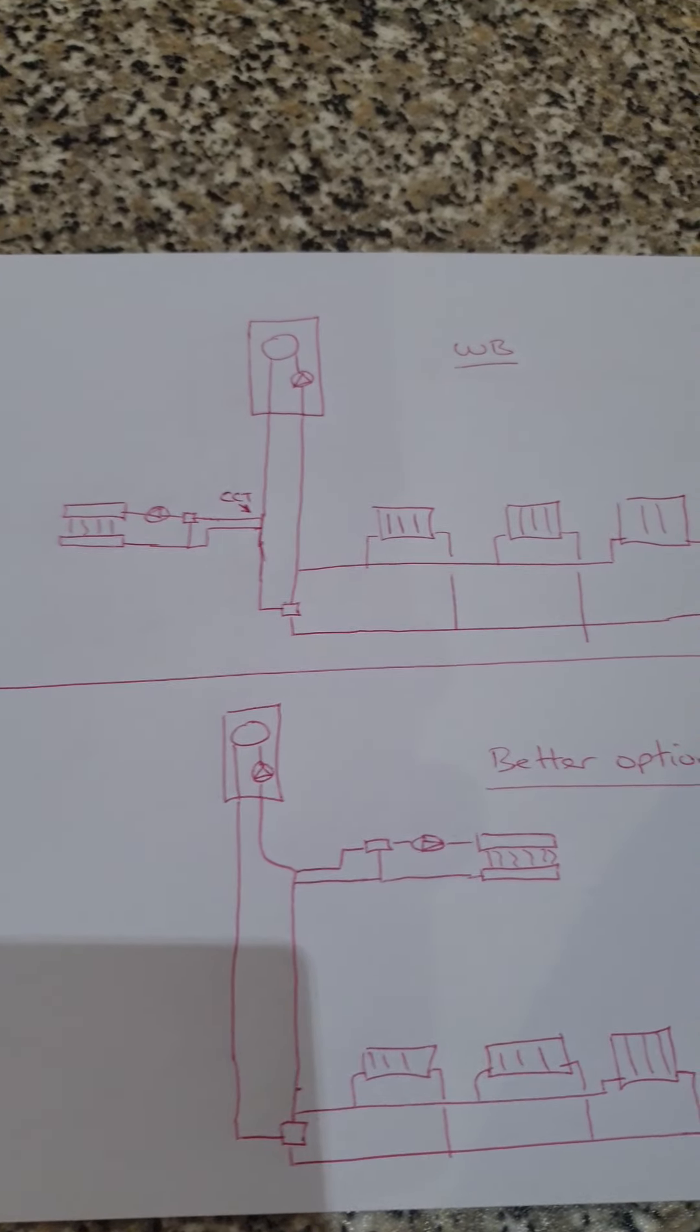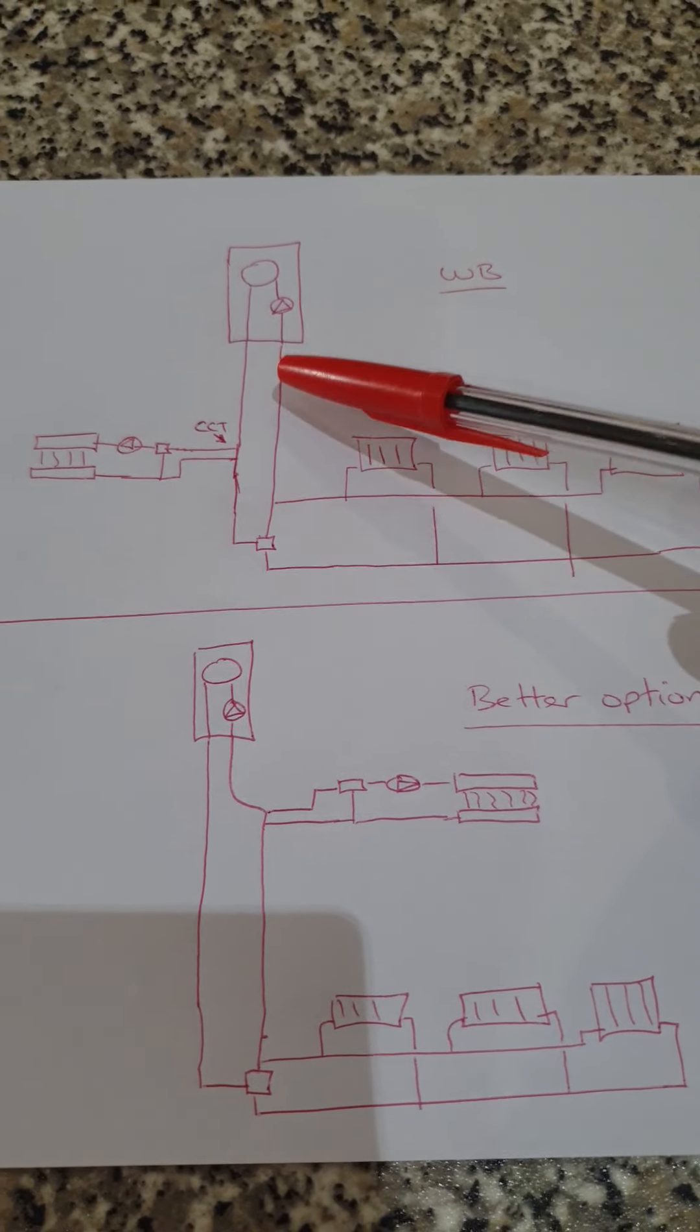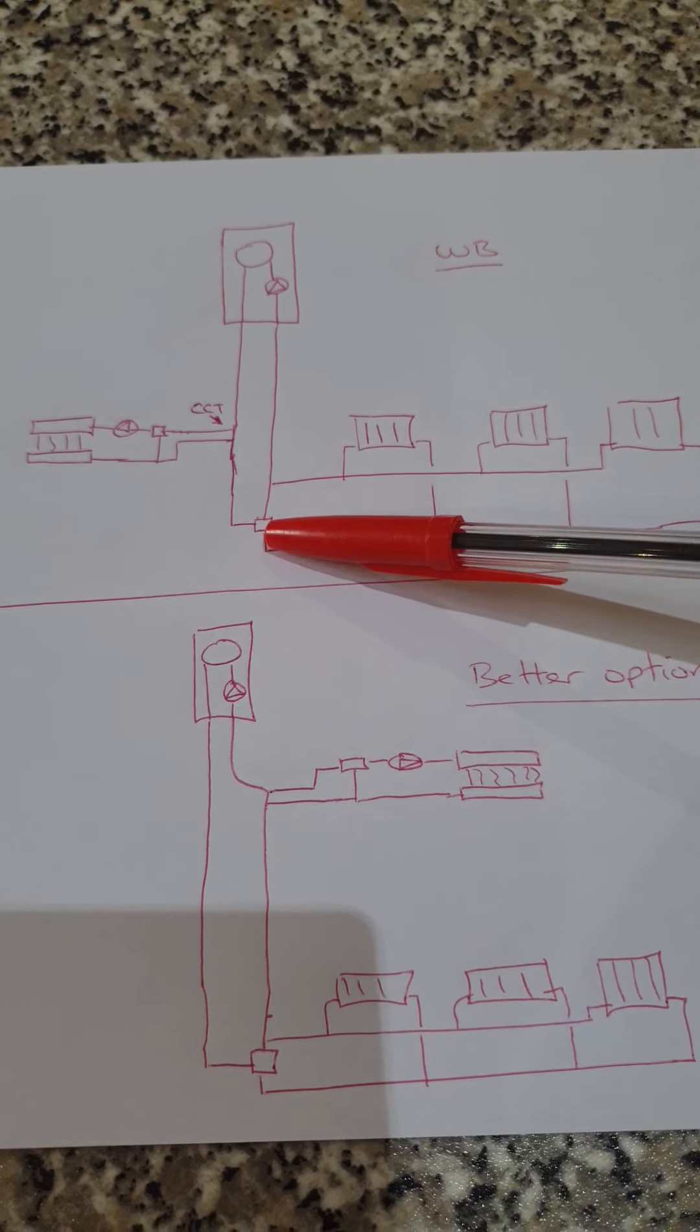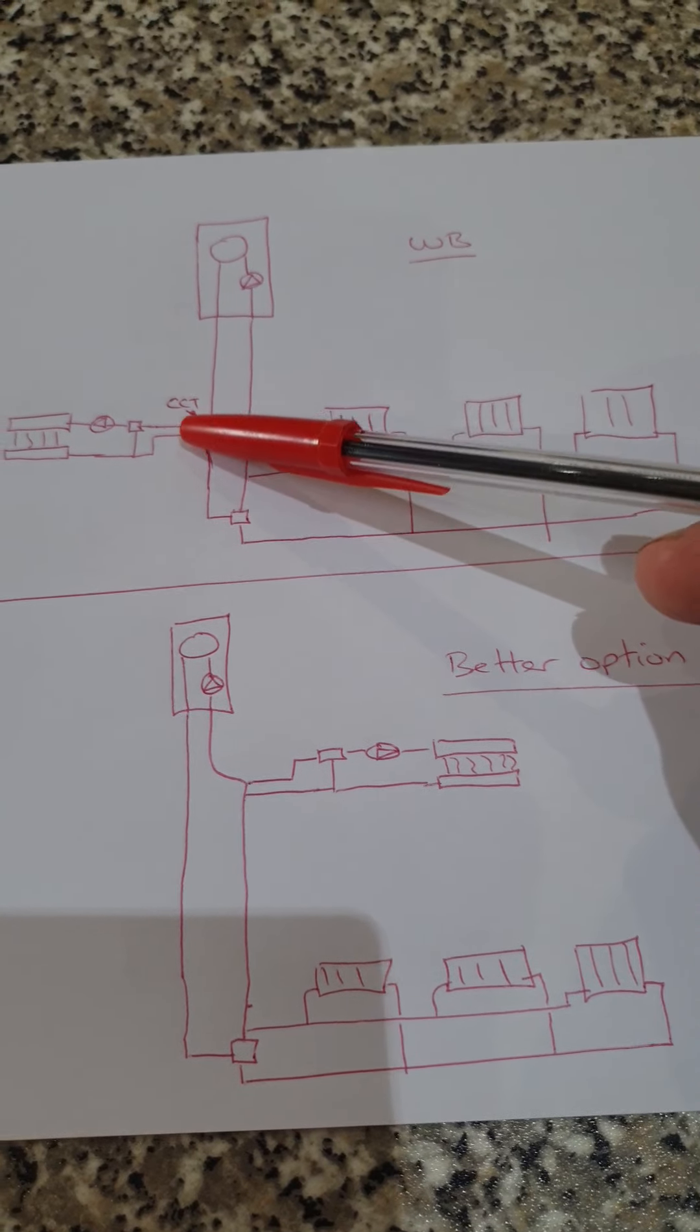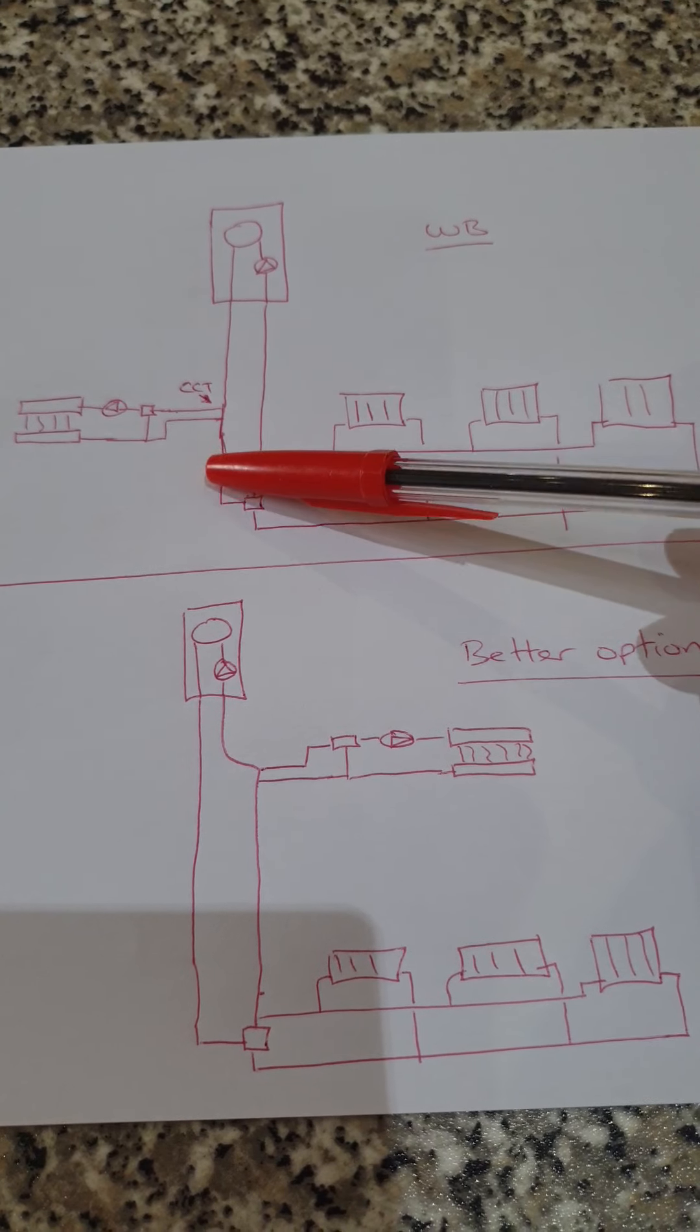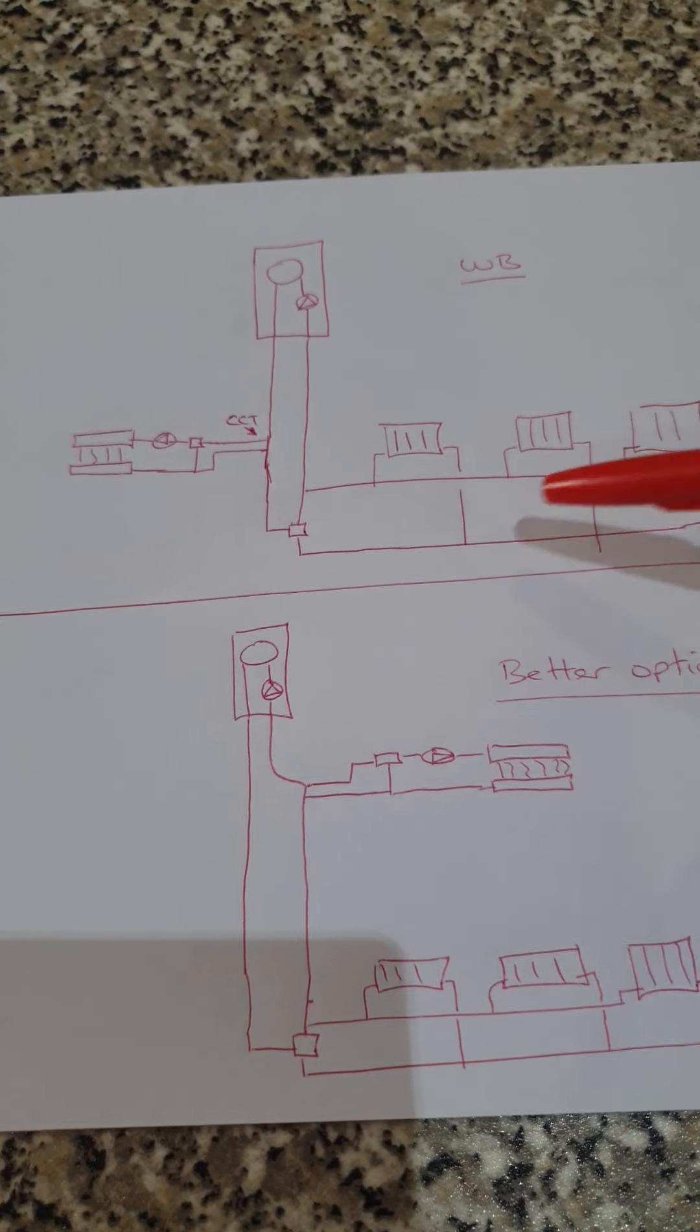Worcester Bosch have come up with a very clever little idea. I do think this is a good idea. I think it's slightly wrong. They've used close coupled T's. Then they've used a diverter valve on the radiator circuit. So, the underfloor heating circuit here is always basically hydraulically separated from the heating system, which works well.